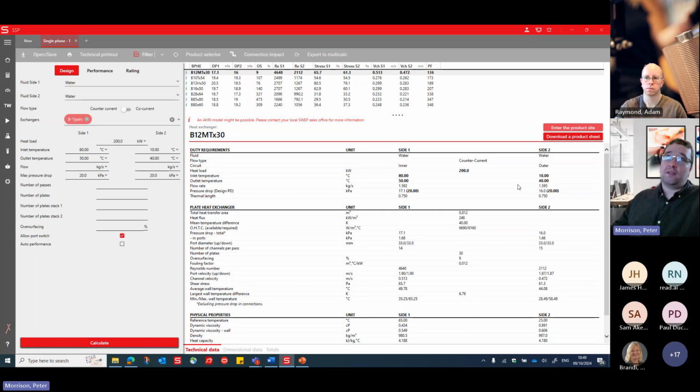And the distance would be the size of the unit. So in this case, it's saying the unit is 9% bigger than it needs to be. So the distance is 9% bigger than what you need. Therefore, the time they're passing each other would be 9% longer. So as a result, the temperature change that you need will be slightly higher in reality.